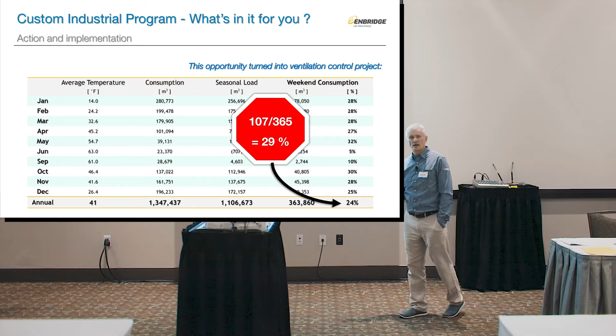So, for example, let's talk about some of the projects we've seen. Remember that opportunity we discussed, 24% consumption during weekends, about 300,000, or 25% of their total consumption? That turned into a ventilation control project. The customer wouldn't believe me that they were actually using this, so luckily he lived close to the facility and went in on two subsequent Sundays when nobody was there. Lo and behold, all the makeup air units were operating, full blast, all of them.